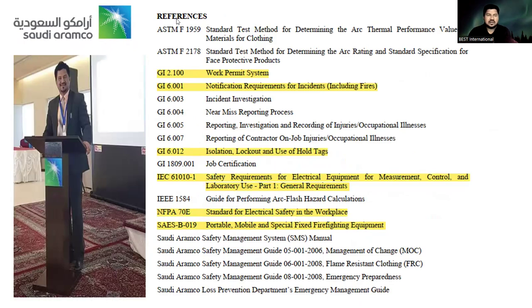These are some of the references of this training, like GI 2.100 Work Permit System, 6.001, the notification requirements for incidents, and also Lockout Tagout 6.012, and safety requirements for electrical equipment from IEC 61010. That's why there is Zone 0, Zone 1, 2, all are mentioned, in a way, and fire protected, explosion proof, fireproof, such equipment is being used. Even arc proof. IEEE guide for performing arc flash hazard calculation. NFPA is also helping us, standard for electrical safety in the workplace, like NFPA 70E, and even portable, mobile, and special fixed firefighting equipment. Saudi Aramco engineering standards B19 is also helping.